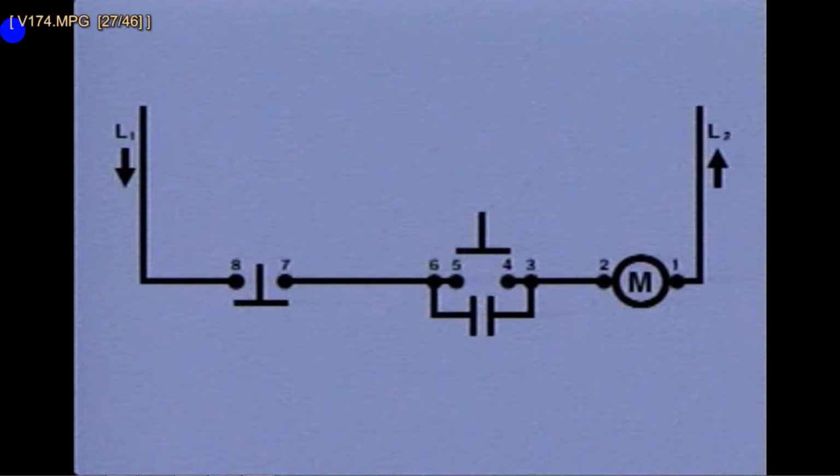Now let's look at another example that's a little more involved. We'll use a simplified schematic of a controller's control circuit to see how you can troubleshoot an energized controller that has a malfunctioning stop button. This simplified diagram represents the controller's control circuit. The malfunctioning stop button is represented in the open position. The electrical connection points shown on the diagram are numbered from 1 through 8 for ease of reference.